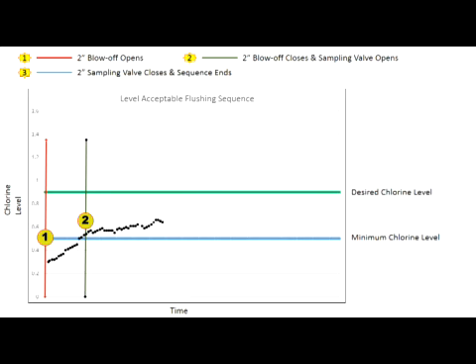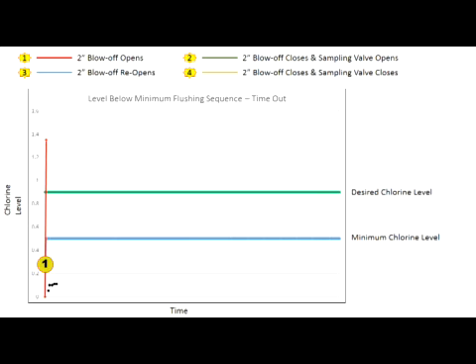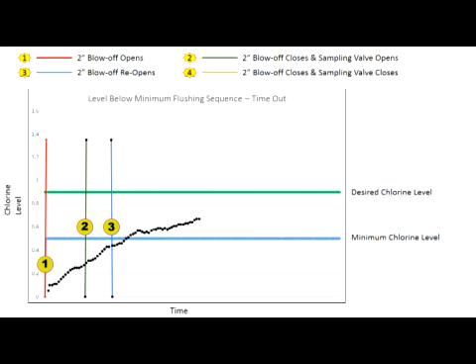Initial and final chlorine levels, time of day, and flush duration data is recorded onto the PLC and is available for download onto the microSD card. A third scenario: if sampled water residual level is below the program minimum chlorine level, the unit will begin to flush and continue to sample. If the sample does not achieve the program desired residual level, the unit will continue to flush until the programmed maximum total flushing time has been reached. Both valves will close, ending the sampling sequence.